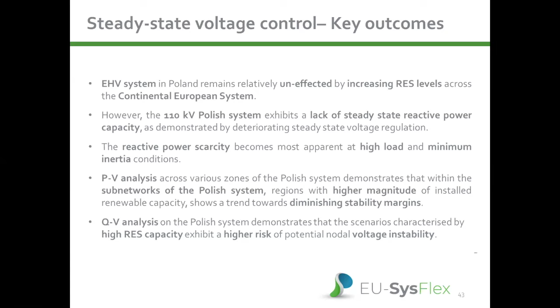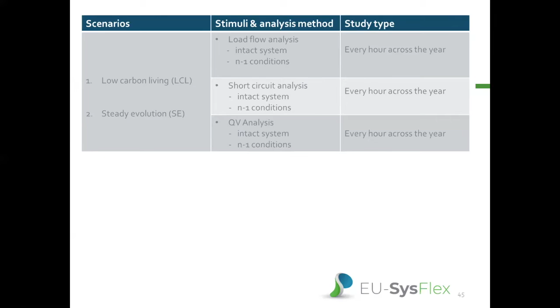Thank you, Matthias. The steady state voltage control has also been analyzed for the Ireland and Northern Ireland power system. That analysis has been done for 2 scenarios, as is all analysis. 3 types of analysis have been carried out, with load flow analysis and QV analysis focused on identifying a potential steady state reactive power scarcity, and a short circuit analysis focused on system strength or dynamic reactive injection scarcity. The analysis has been carried out across every hour of the year, both for N-1 and intact system conditions.